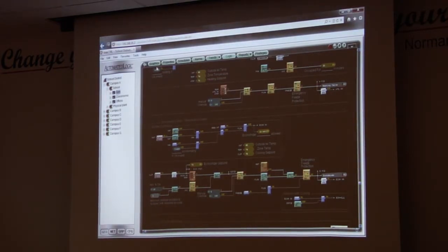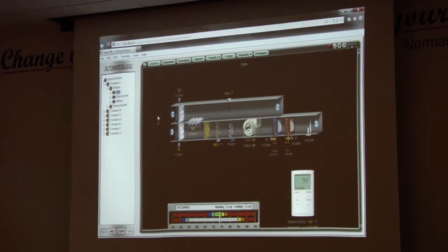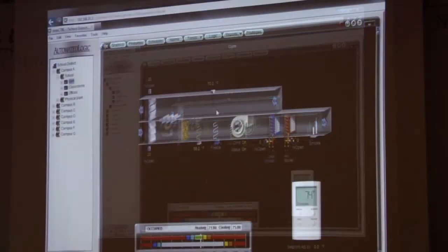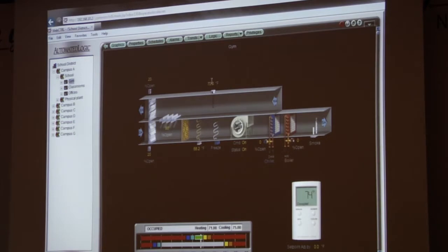All right, so now let's take a look at my graphic. We're still going around. Did everybody get their return air temperature locked at some value? Probably in the 70s. So now my return air temp is 70 degrees. My outside air economizer is now opened up to 20 and 80. I don't have a filter alarm on here. My mixed air temperature is about 55 degrees. I'm not in a freeze condition. My supply fan says on and the status is on.